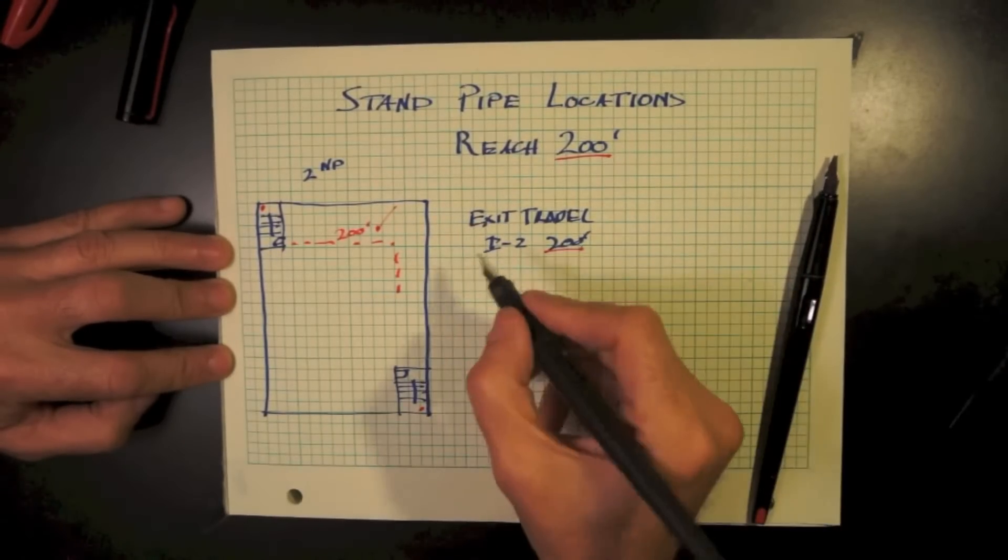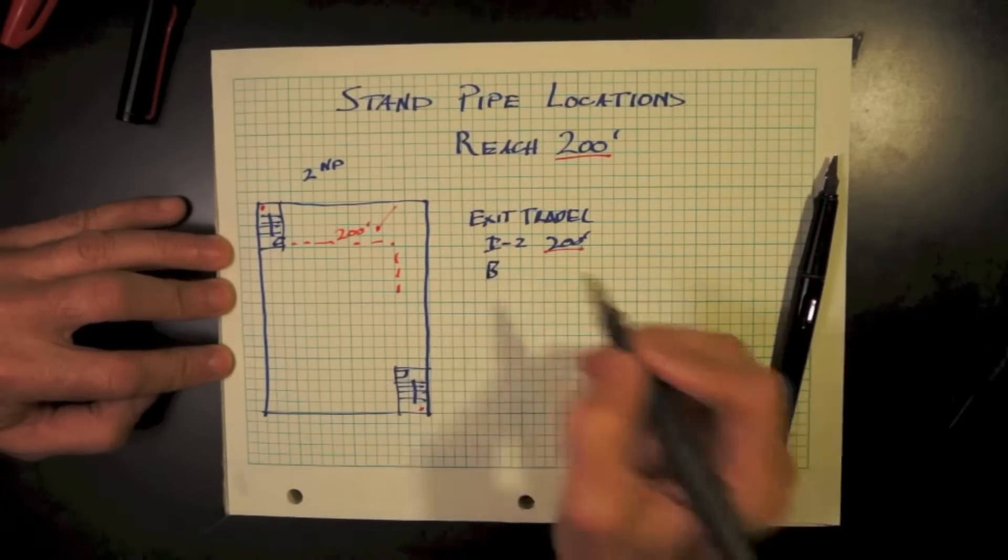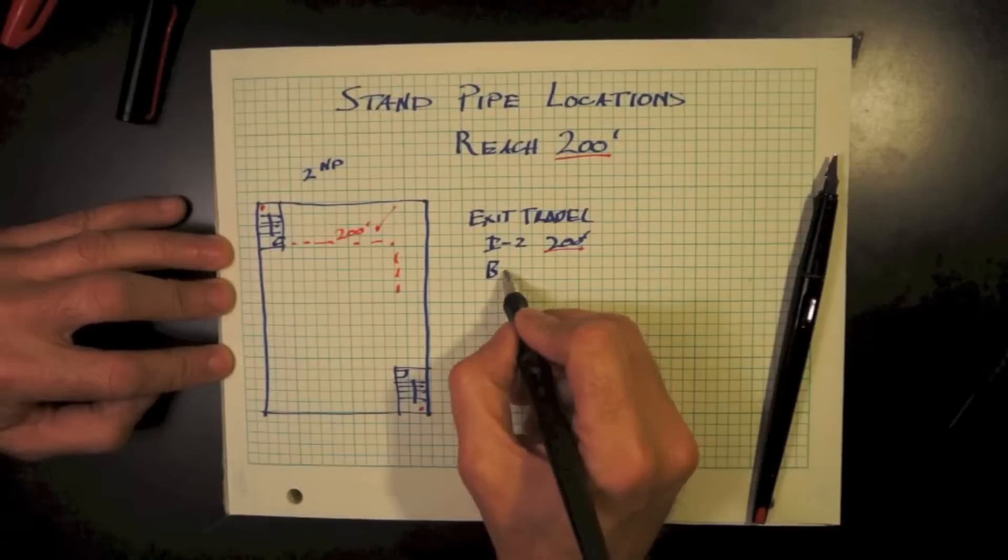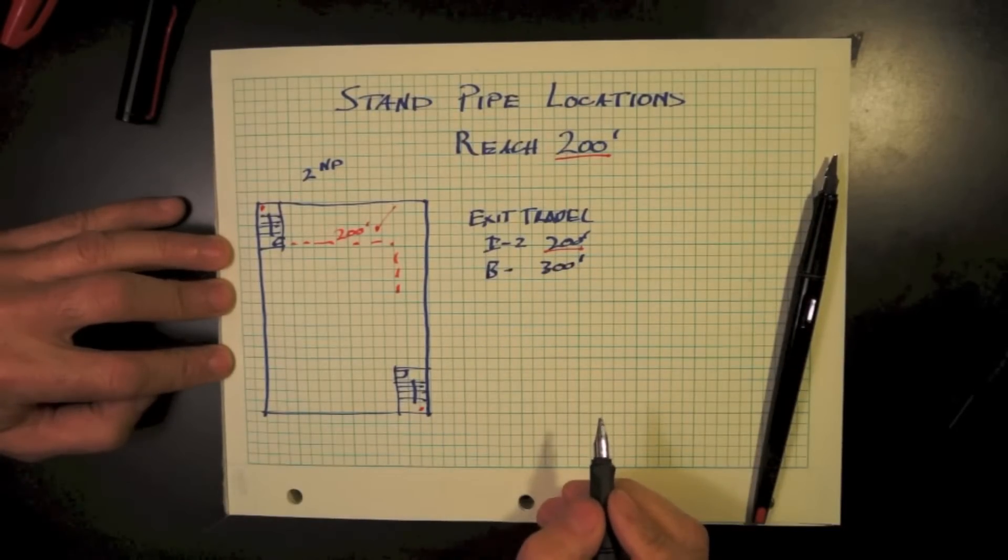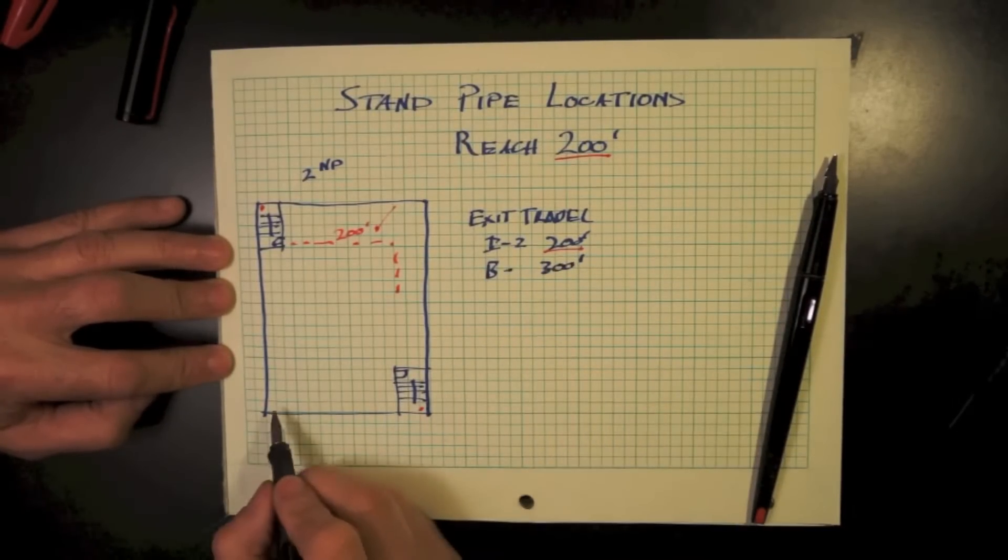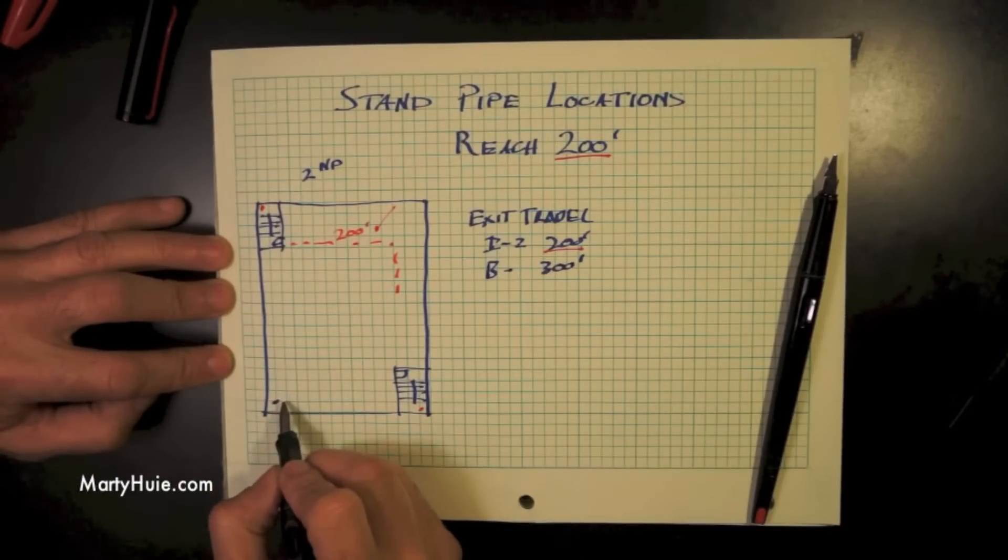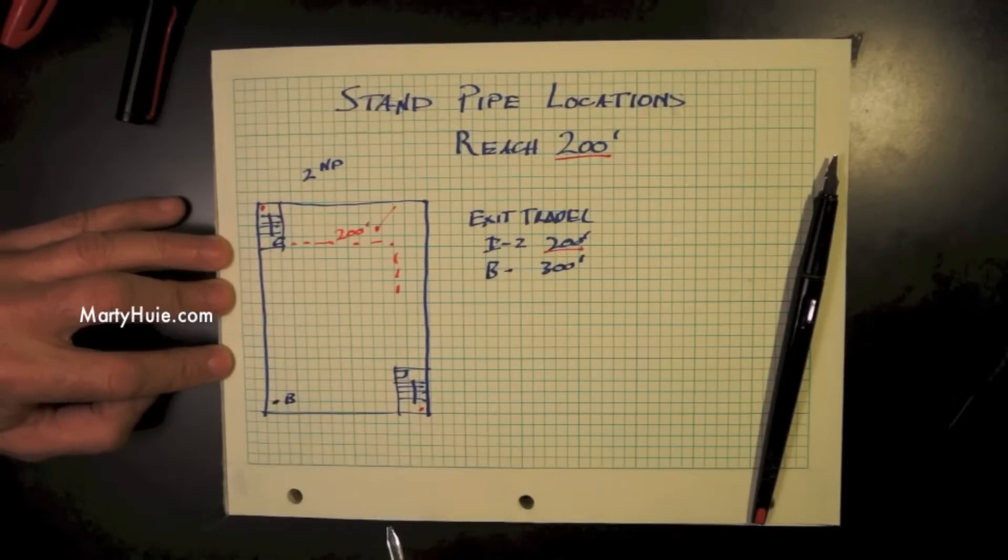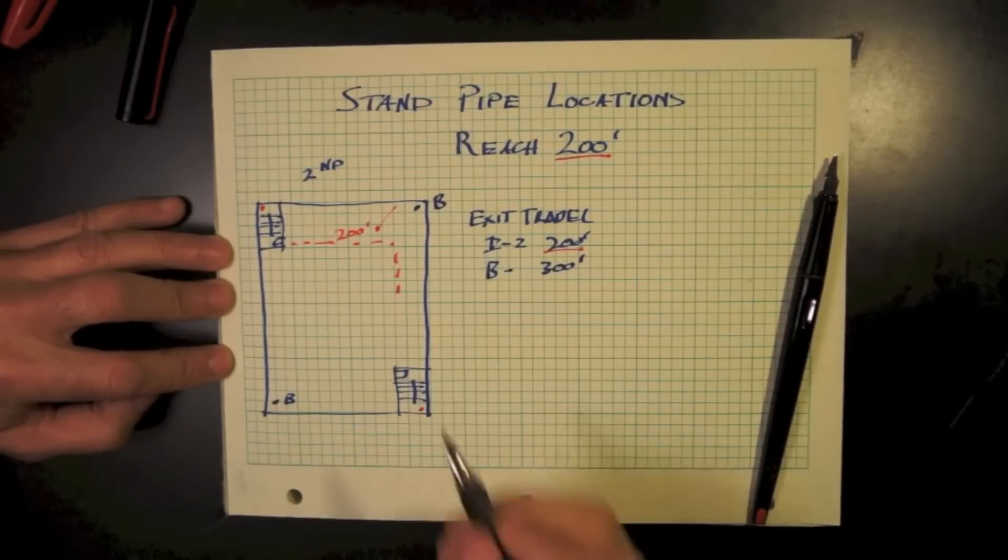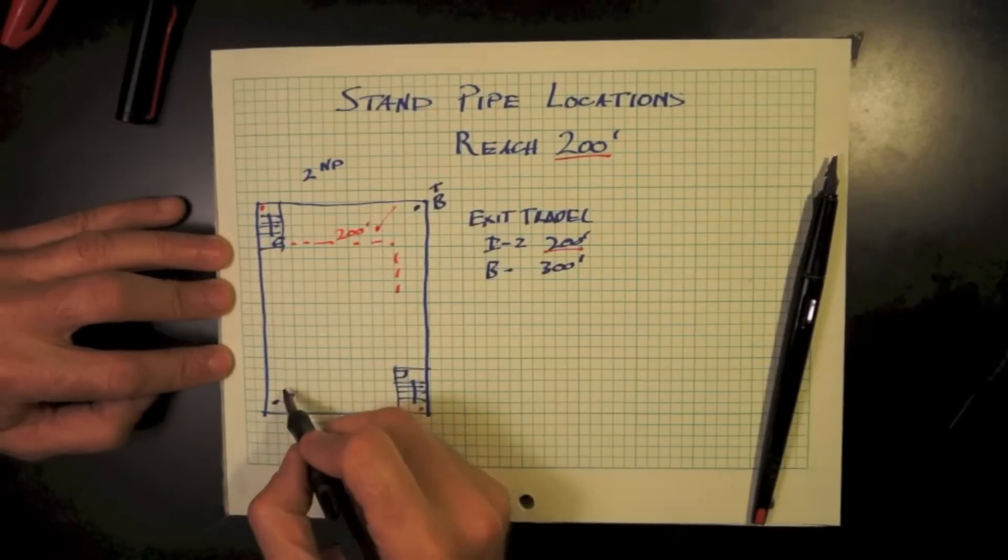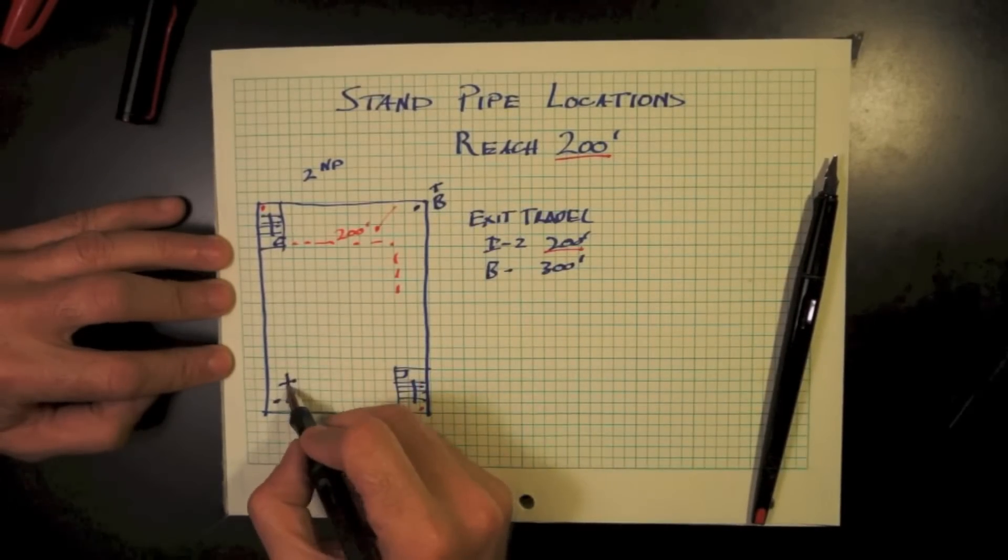In other healthcare occupancies, other than I-2, in B occupancy, our travel distance is 300 feet. Therefore, you will need additional standpipes in order to access a standpipe within 200 feet. Just because the travel distance to an exit increases does not mean the travel distance to a standpipe has increased.